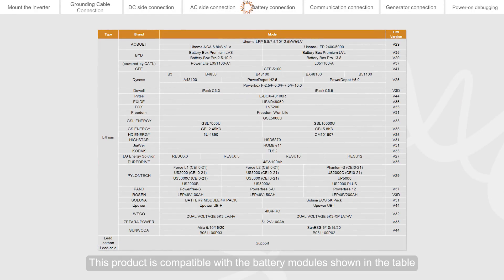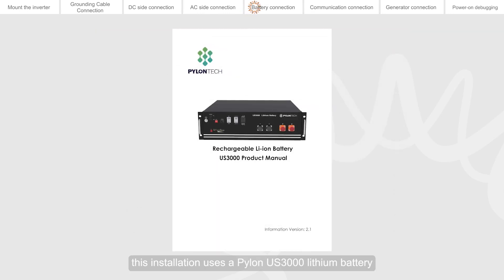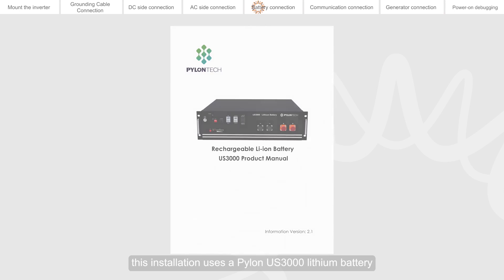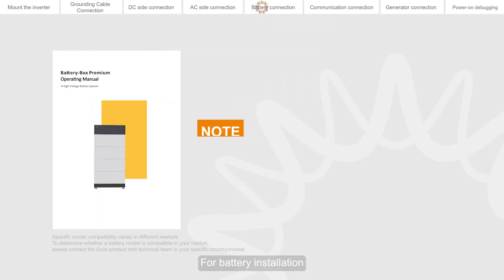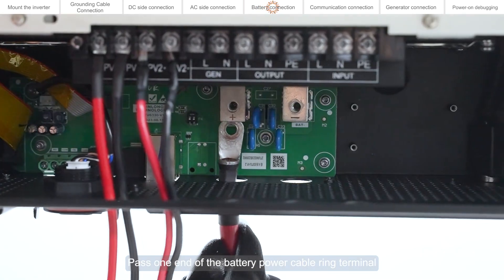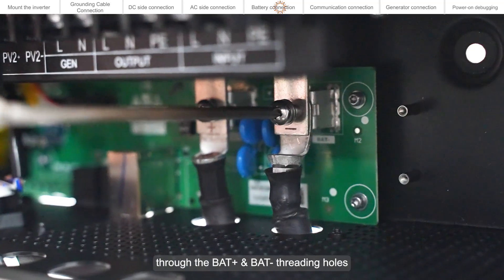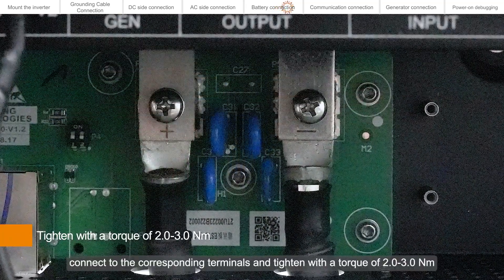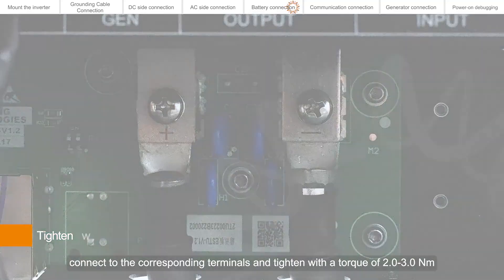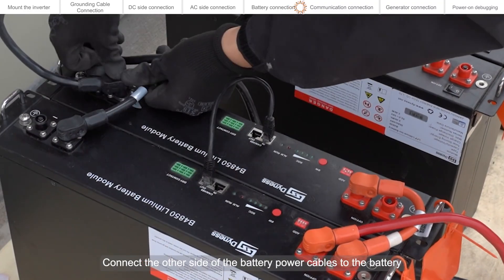This product is compatible with the battery modules shown in the table. This installation uses a Pylontech US3000 lithium battery. For battery installation, please refer to the battery manufacturer's instructions. Pass one end of the battery power cable ring terminal through the BAT+ and BAT- threading holes, connect to the corresponding terminals, and tighten with a torque of 2.0 to 3.0 Newton-meters. Connect the other side of the battery power cables to the battery.